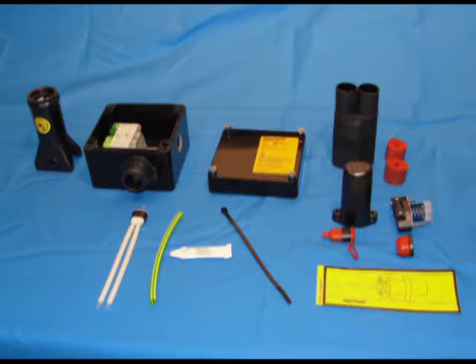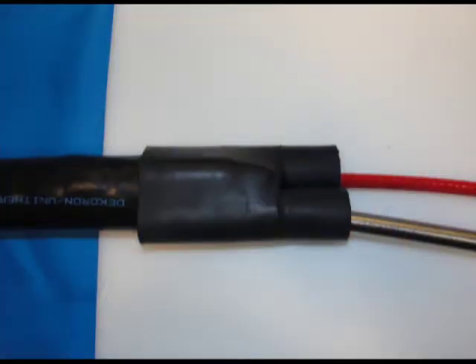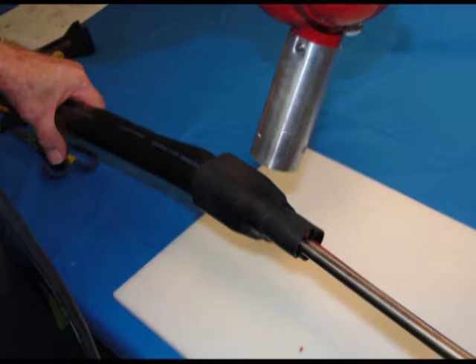Please ensure that you follow the current manufacturer's instructions that come with the components. The first step is to confirm that the components utilized have the appropriate approval ratings for the country and area you are installing them in. We will briefly cover the required steps to properly seal the tubing bundle with a heat shrink boot. Slide the shrink boot down over the heat tracing and shrink into place. A properly sealed bundle will eliminate moisture ingress into the bundle.